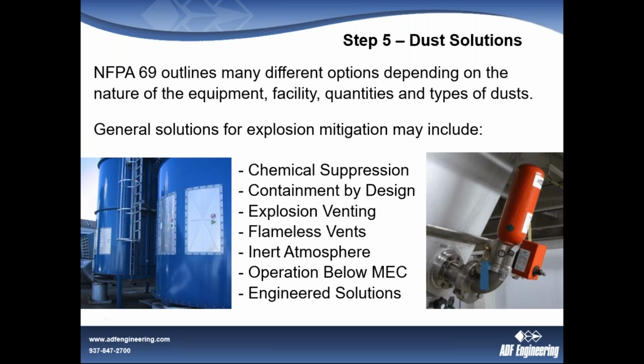Inerting, operating below the explosive concentration, these are some other things I mentioned. So engineered solutions are allowed. So if an engineer can come up with a less expensive way, all you have to do is document that, and the risk that remains after implementing that solution, you just document that, and that's acceptable.